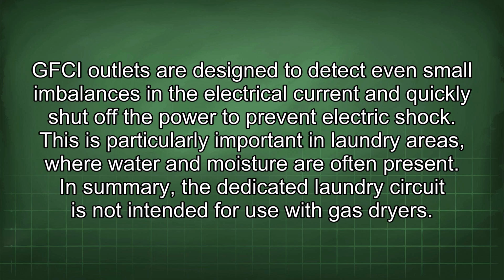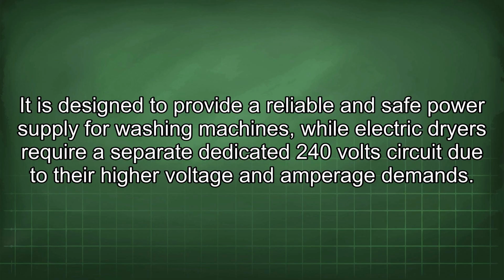In summary, the dedicated laundry circuit is not intended for use with gas dryers. It is designed to provide a reliable and safe power supply for washing machines, while electric dryers require a separate dedicated 240-volt circuit due to their high voltage and amperage demands.